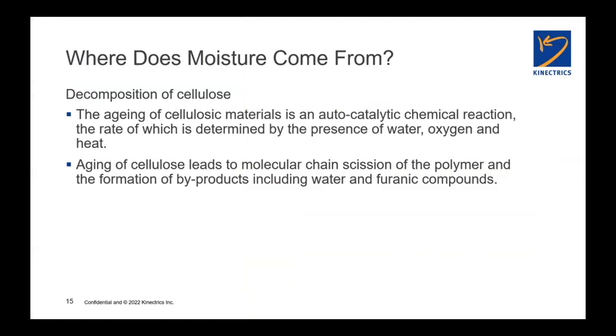I already mentioned this, but we're talking about the decomposition of cellulose being an autocatalytic chemical reaction. So the rate of that chemical reaction is determined by the presence of oxygen, heat, and moisture, water. And the more we have of any of those three things, the faster the breakdown reaction is going to occur. And we all know that the rate of a chemical reaction is determined by the Arrhenius equation. So a 7 degrees C increase in operating temperature of the transformer halves the life of the insulation system. Conversely, running 7 degrees cooler doubles the life of the insulation system. So it's very strongly thermally driven.